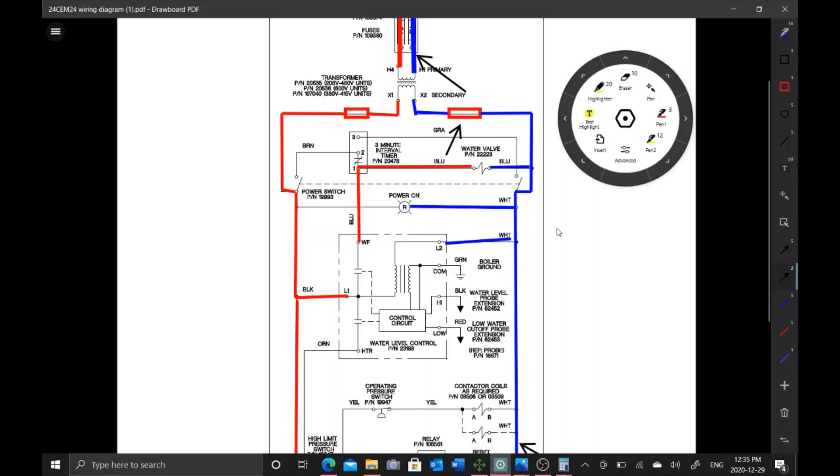Based on I had those fuses hooked up in line, it didn't matter to me how many attempts it took me, because at this point I wasn't blowing the transformer. Very interesting service call. Blew three of those super expensive transformers. I wasn't brought into the loop until the third one was blown. At that point it was, no troubleshooting over the phone, let me just get on site and figure out what's going on. From studying that schematic, I figured out there's only four possibilities: the water board, the fill solenoid, that transformer, or the power light. What I've done at that point is I put some fuses in line. I always keep those fuse holders in my truck. It's common on the Henny Penny fryers that you blow those transformers on the 24-volt circuit. Usually it's the solenoid or the gas valve.